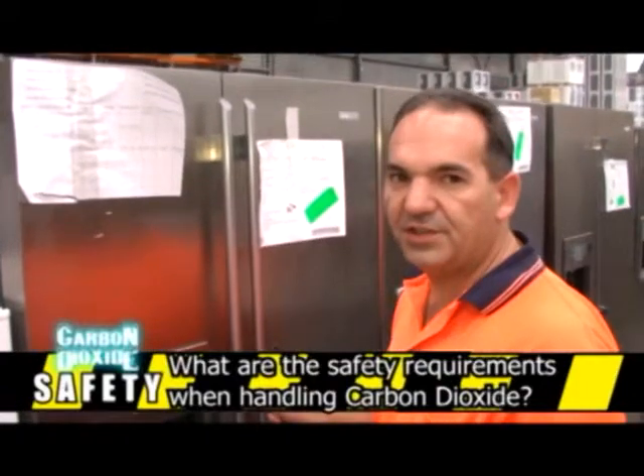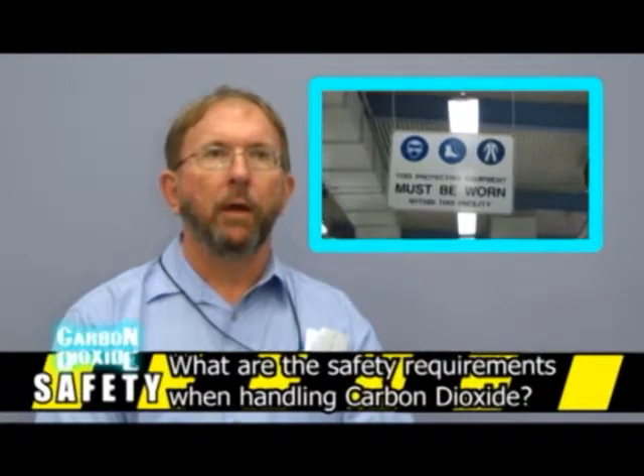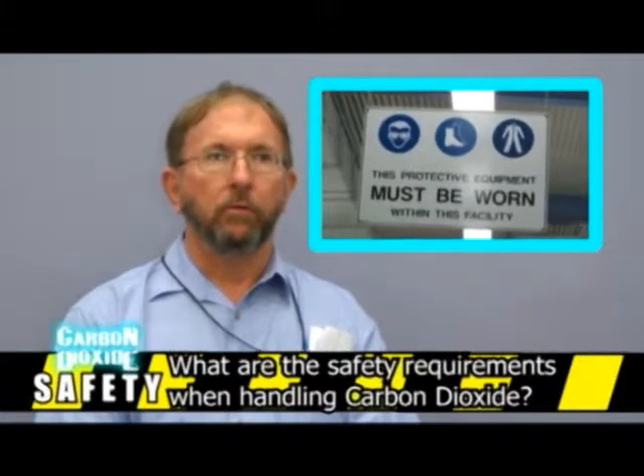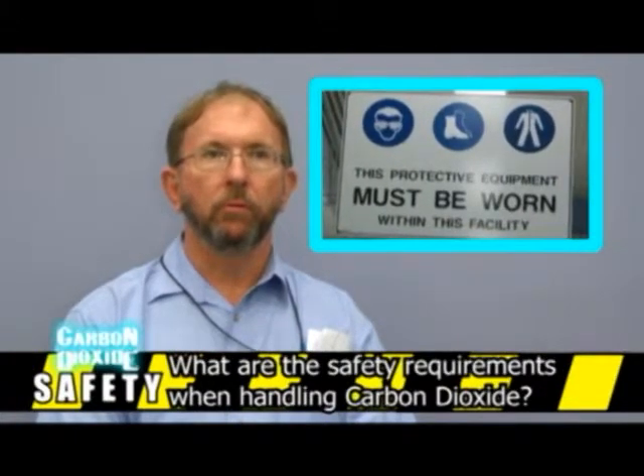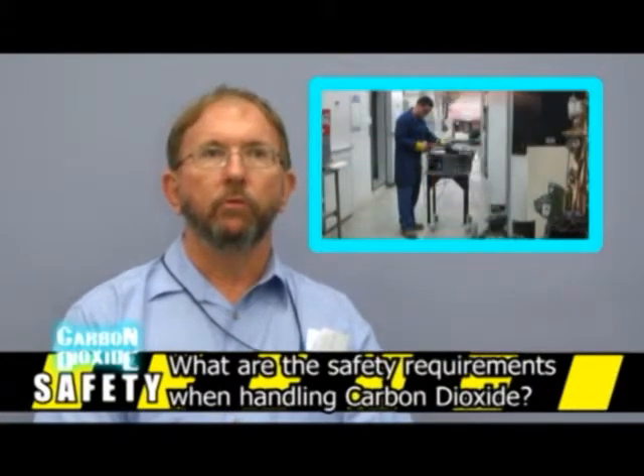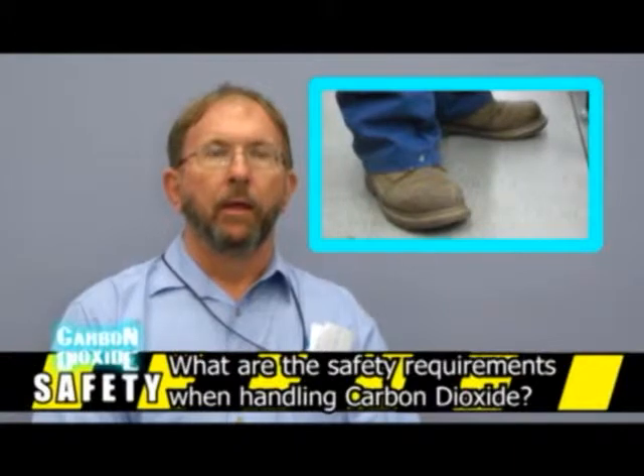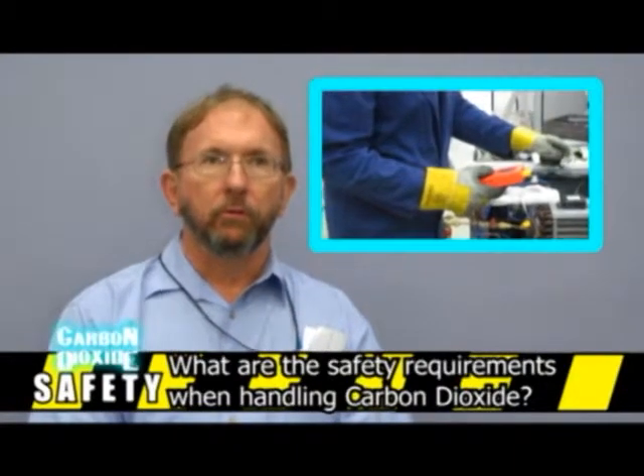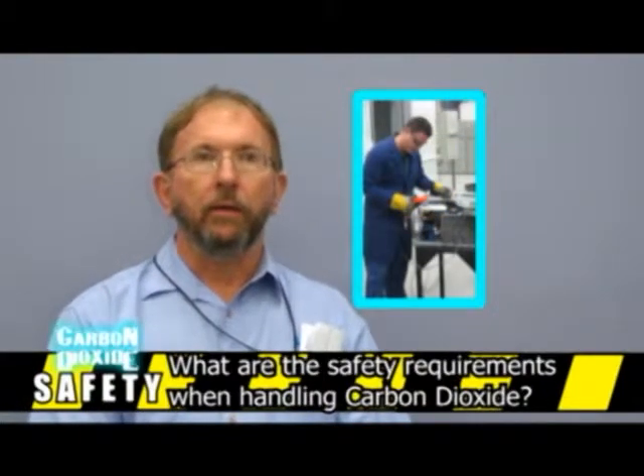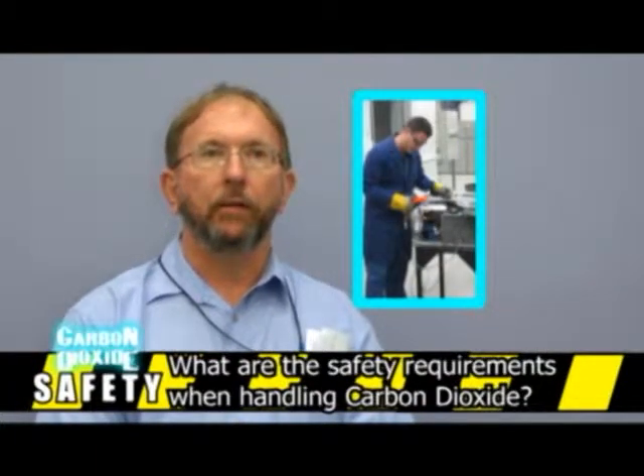What are the safety procedures required for handling CO2? Carbon dioxide is classified as an A1 refrigerant, as all other refrigerants that we commonly use are. So all PPE is applicable, such as safety glasses, which must be worn at all times, and protective clothing, which includes long trousers, long sleeve shirts and safety boots. It must also be remembered that carbon dioxide is an asphyxiant, which means that it displaces oxygen in the air and can lead to suffocation. So we must work in a very well ventilated area.